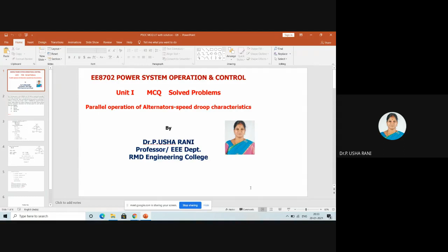The question gives us two generators rated at 400 megawatt and 700 megawatt operated in parallel. The speed droop characteristics of their governors are 3% and 4% respectively from no load to full load. Assuming that the governors are operating at 50 Hz at no load, how would a load of 1000 megawatt be shared between them? What will be the system frequency at this load?